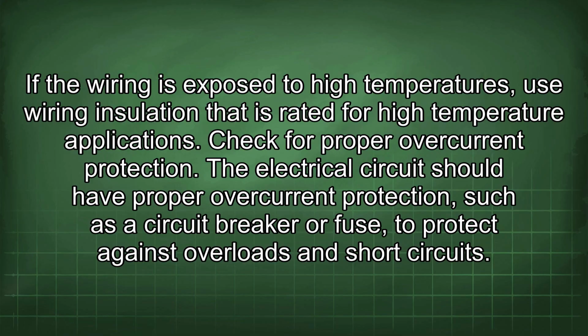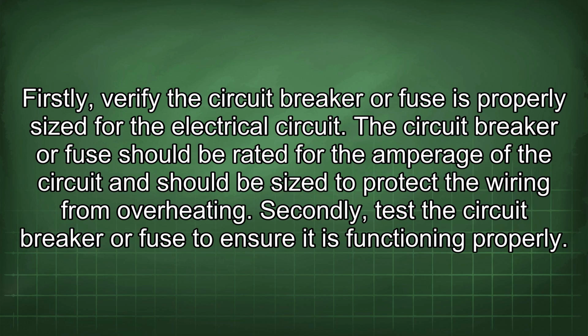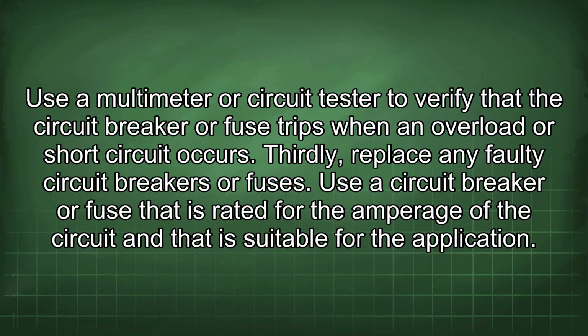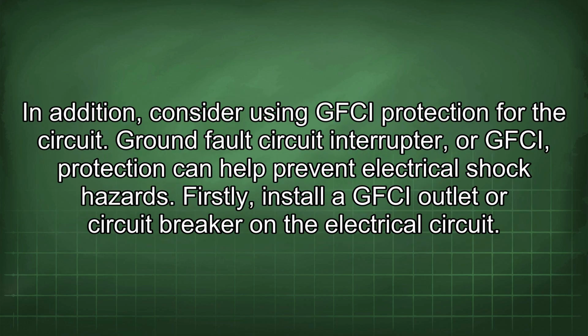short circuits. Firstly, verify the circuit breaker or fuse is properly sized for the electrical circuit. The circuit breaker or fuse should be rated for the amperage of the circuit and should be sized to protect the wiring from overheating. Secondly, test the circuit breaker or fuse to ensure it is functioning properly. Use a multimeter or circuit tester to verify that the circuit breaker or fuse trips when an overload or short circuit occurs. Thirdly, replace any faulty circuit breakers or fuses. Use a circuit breaker or fuse that is rated for the amperage of the circuit and that is suitable for the application. In addition, consider using GFCI protection for the circuit.